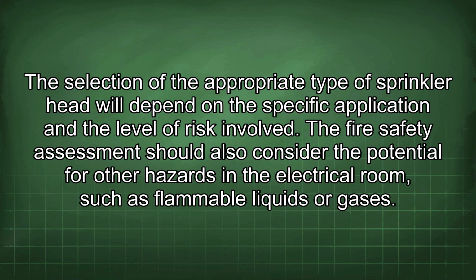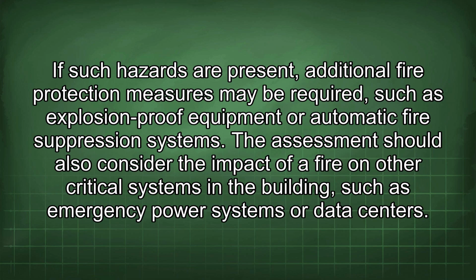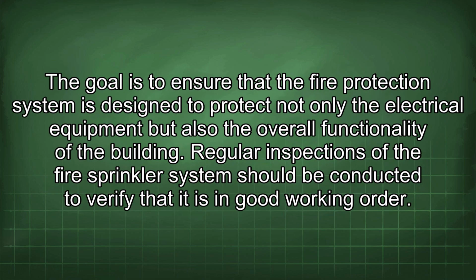The fire safety assessment should also consider the potential for other hazards in the electrical room, such as flammable liquids or gases. If such hazards are present, additional fire protection measures may be required, such as explosion-proof equipment or automatic fire suppression systems. The assessment should also consider the impact of a fire on other critical systems in the building, such as emergency power systems or data centers. The goal is to ensure that the fire protection system is designed to protect not only the electrical equipment, but also the overall functionality of the building.